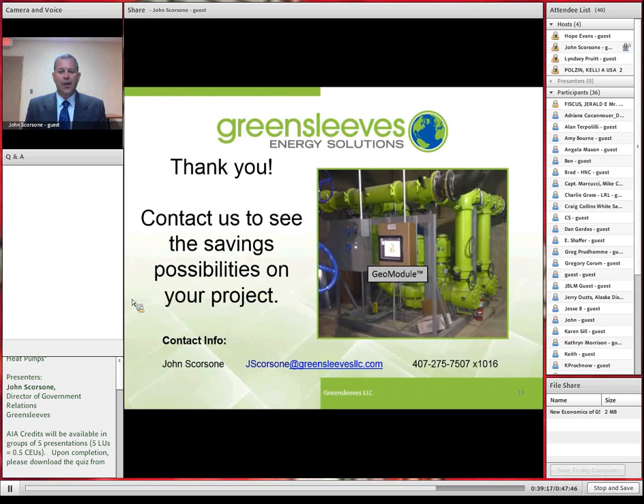Regarding heat rejection required - remember, if you size it for peak load on a hybrid, what the typical hybrid is doing is you have so much capacity in the ground, and when that ground gets too hot, you use the hybrid in summer to get rid of extra heat. But that occurs at the worst time of year to operate that cooling dominant system. What we want to do is manage that loop temperature lower and operate the hybrid in the off-season. It might be slightly bigger than a traditional hybrid used in summer, because we want to pump as much volume of heat through that device at the lowest energy cost point in winter.